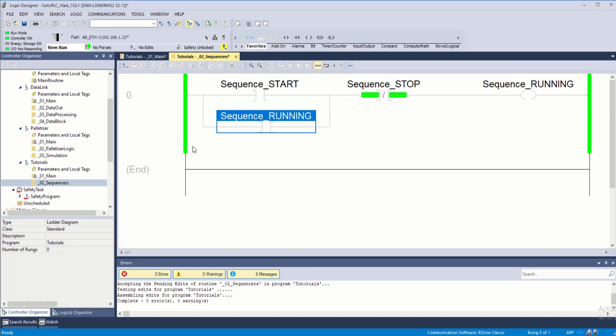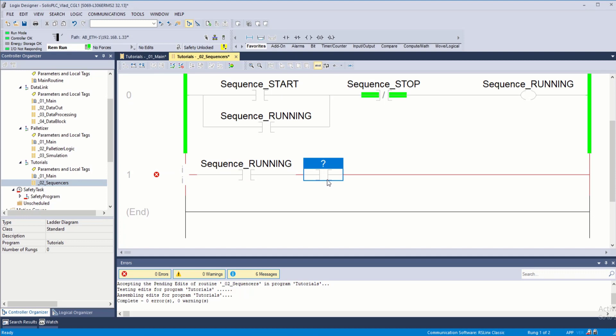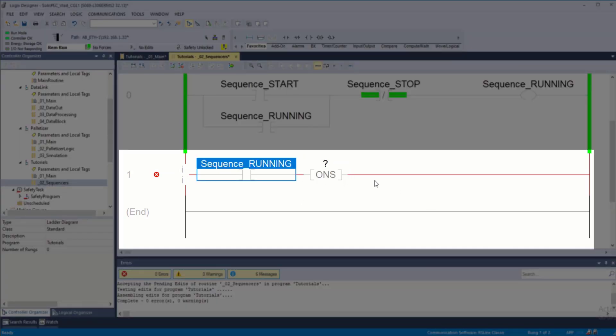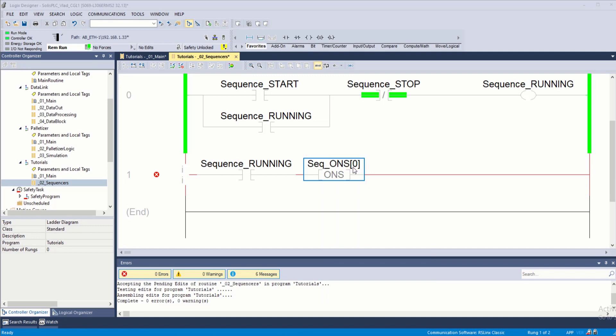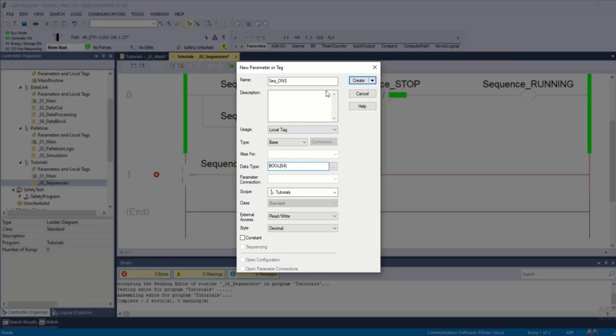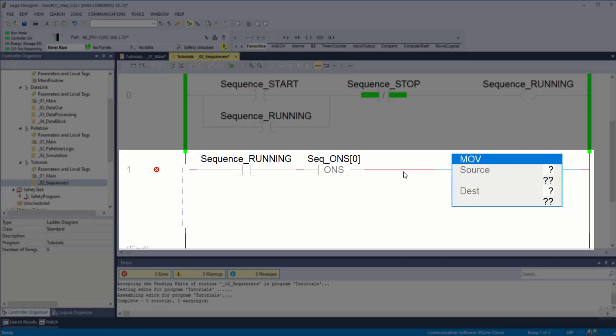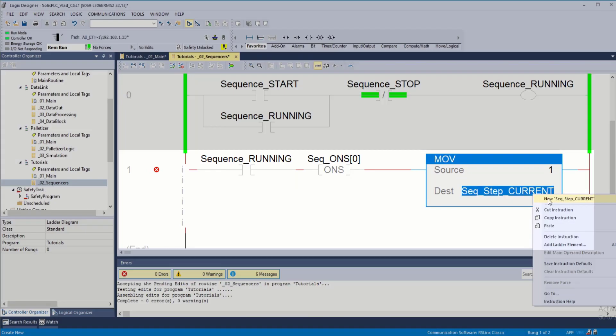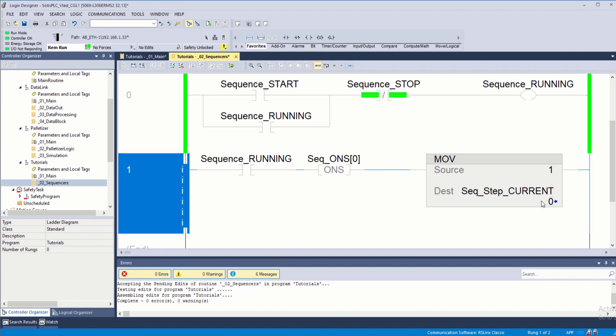Once the sequence starts to run, we need to create the conditions or steps through which it's going to go. If the condition is running, we're going to do a one-shot instruction. I'm going to create an array called Seq_ONS — an array of 64 booleans underneath tutorials. Once it starts running, I want to move step number one into sequence current step — I'll name that 'step current', a double integer underneath tutorials. So once the sequence starts running it puts in a value of one.